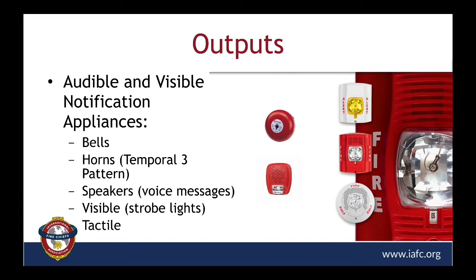Okay, now let's look at output devices or notification appliances. And they provide audible or visible notification of an alarm condition to the building occupants. Now, there are numerous types of alarm notification appliances. Number one, bells. They alert people by the sense of hearing. And really, they operate by causing a striker to contact a steel gong, and this produces a vibrating bell sound.